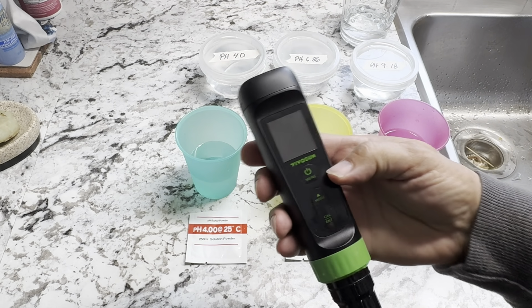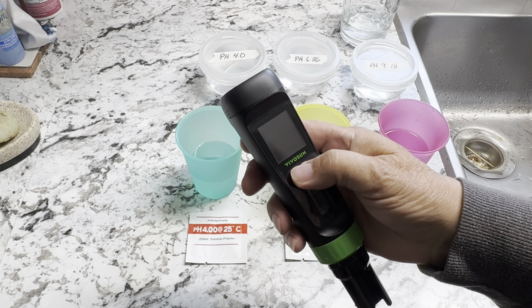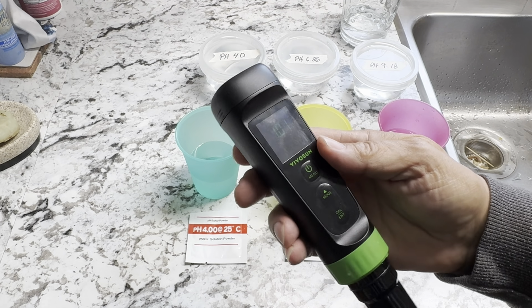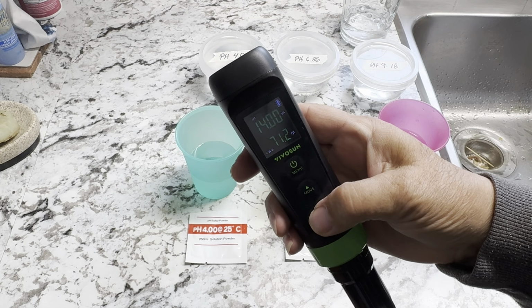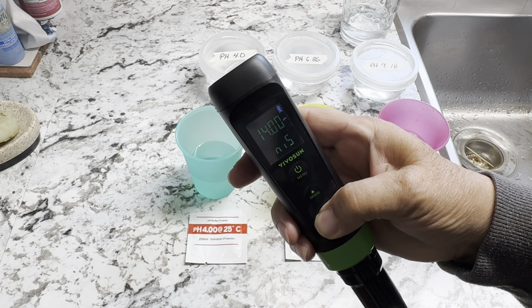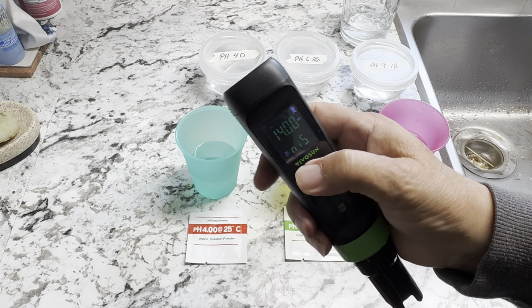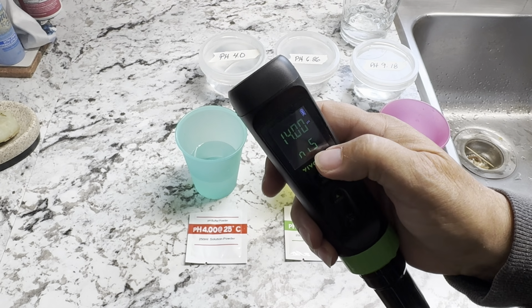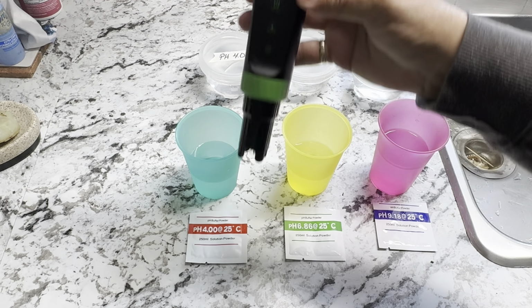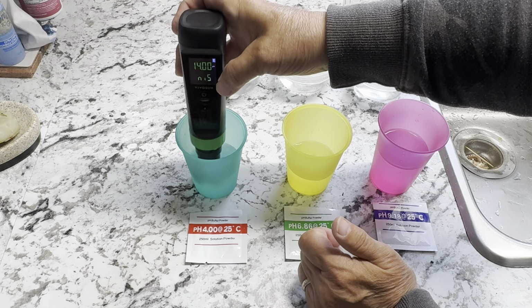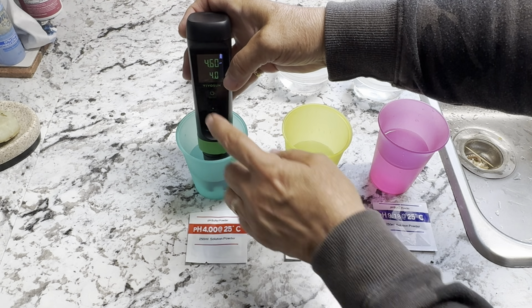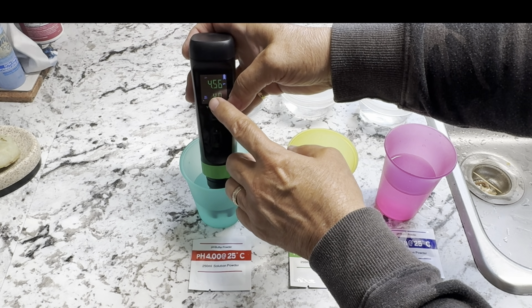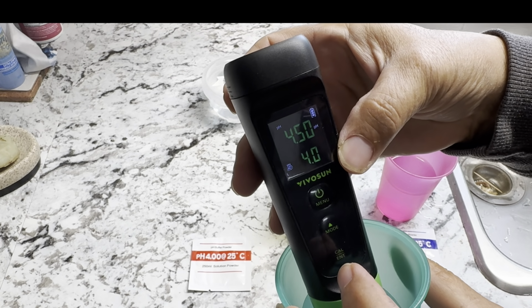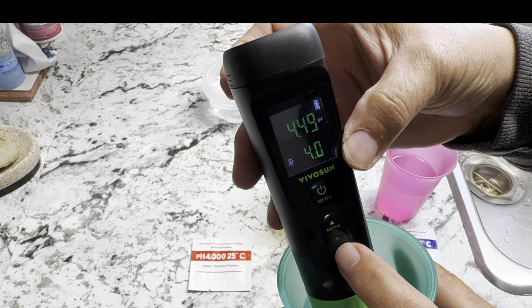Okay, so we are ready to calibrate this meter here. So you just do a quick press here to turn it on, and then do a long press on the calibration button, and that will put it into calibration mode. So there'll be a little thing flashing down here in the corner. So you can start off with the 4.0. So you just simply put it in there and swirl it around. And this little thing in the corner, hopefully you can see that, is flashing. Once it stabilizes and stops flashing, you can press the calibration button.